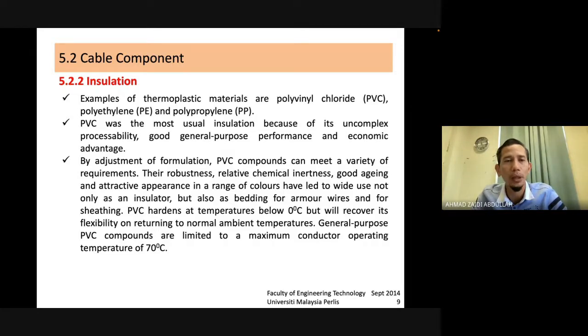Okay, by costing and also fulfilling the standard, so that's why PVC is mostly what you can find lah. So by adjustment of formulation, PVC compound can meet a variety of requirements. Their robustness, relative chemical resistance, ni macam-macam you can read lah all of this part. But this part is important. PVC hardens at temperatures below 0 degrees but will recover flexibility on returning to the normal ambient temperature. So general purpose PVC compounds are limited to a maximum conductor operating temperature of 70 degrees Celsius.